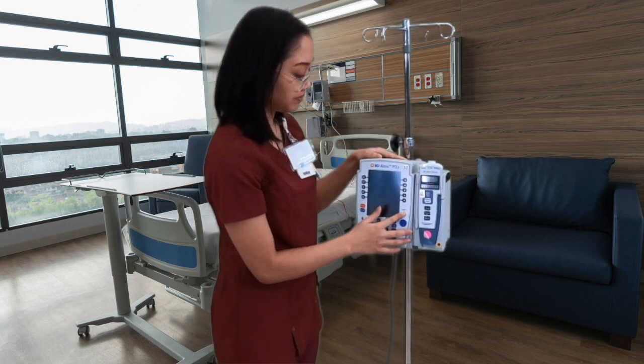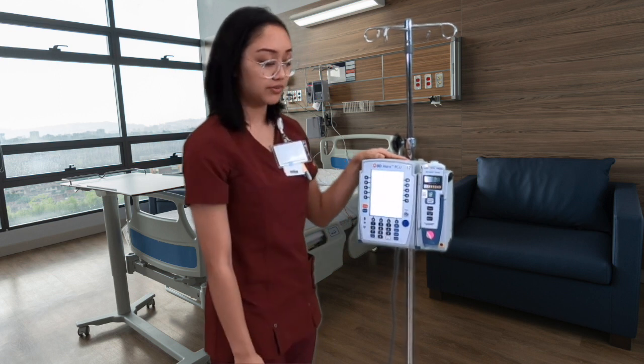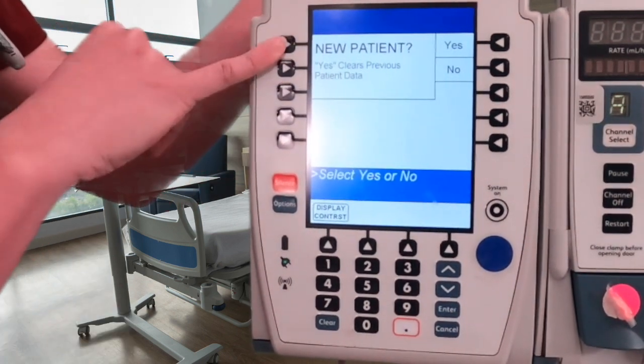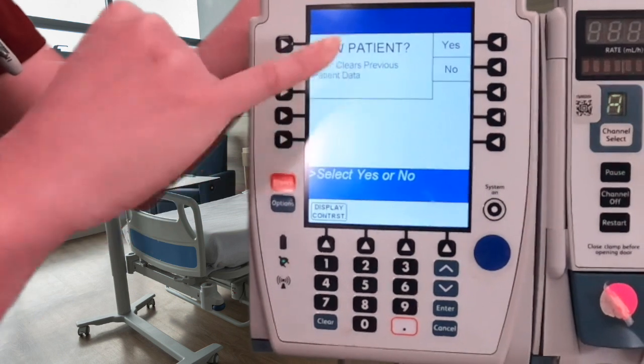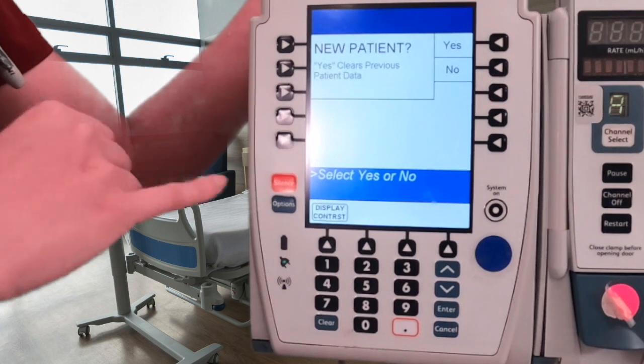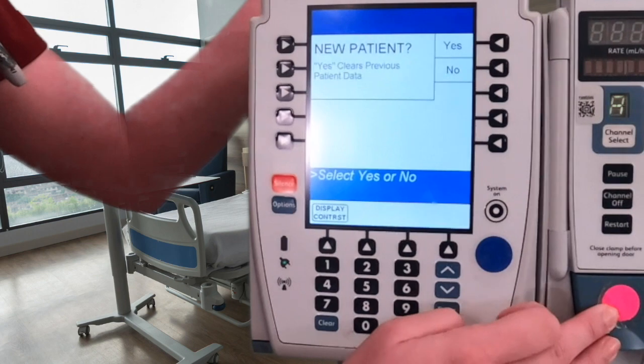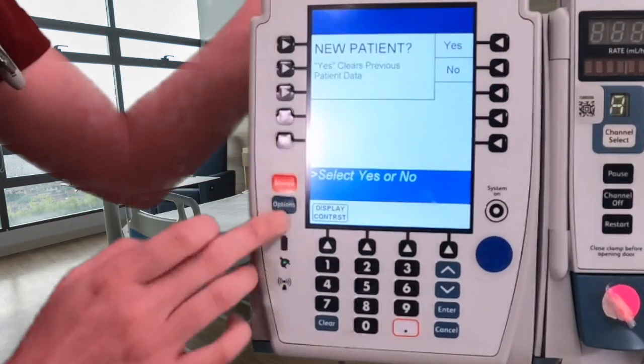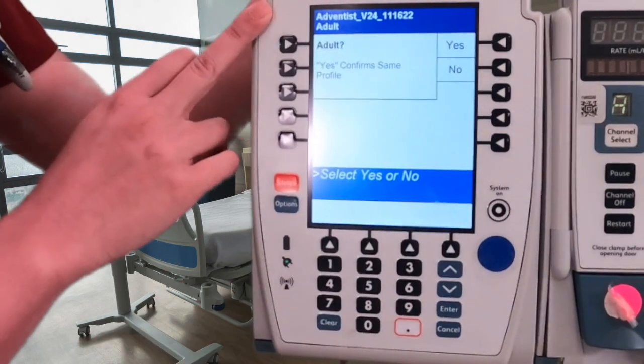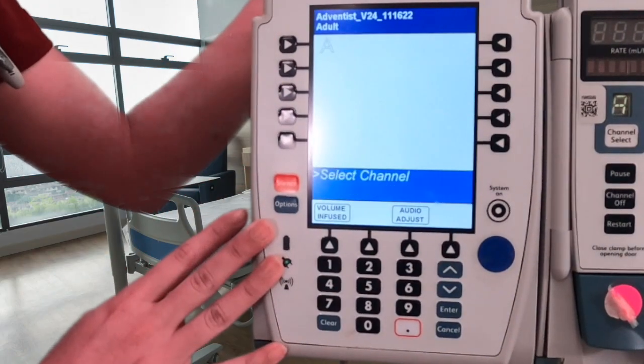Now that we have our channel connected, we can go ahead and turn on our pump. Over here is the system on button — you only have to click it once. Once the pump is on, it will give you a prompt that says 'New Patient.' If you click yes, it will clear the previous patient data. If you are continuously programming scheduled IV fluids for the same patient, press no, but if it is a new patient, press yes.